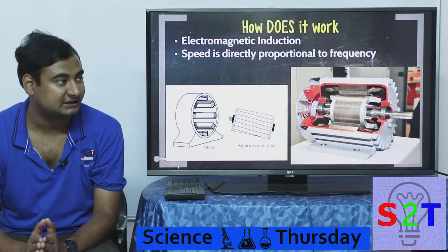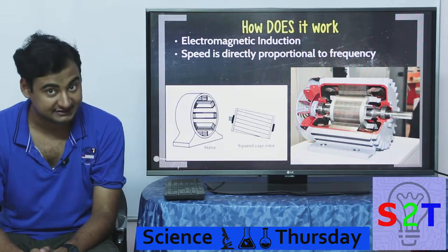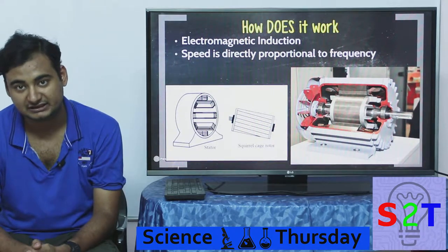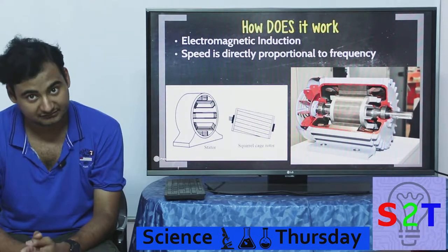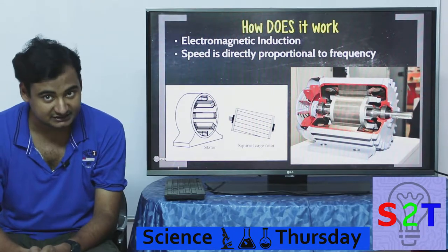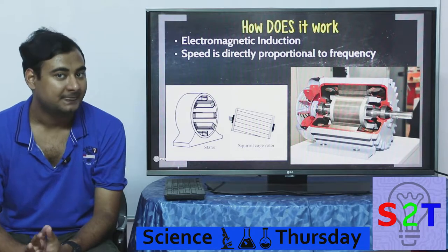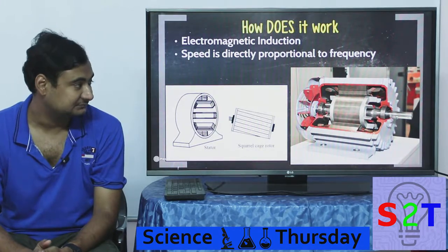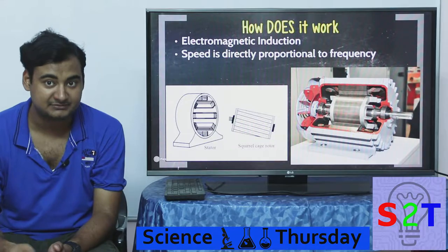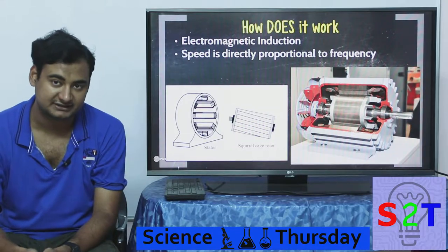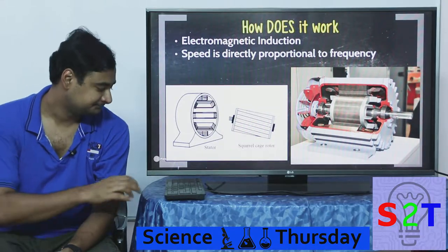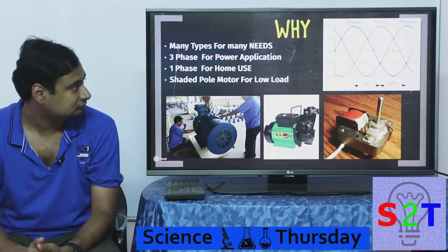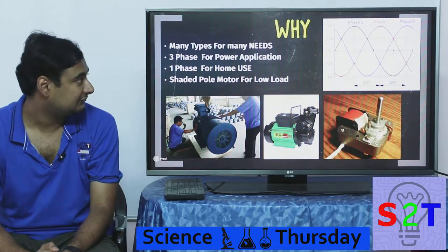The speed of the motor is directly proportional to the frequency. So if you have something running on 50 Hz it will run differently compared to something running at the same voltage but at 60 Hz. You have to pay attention to this: the RPM is directly frequency-dependent.